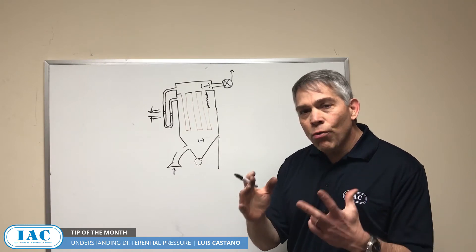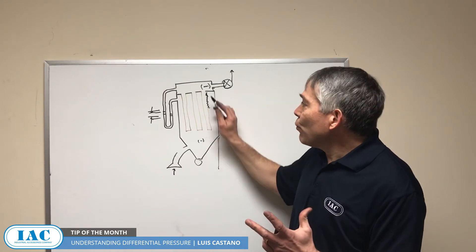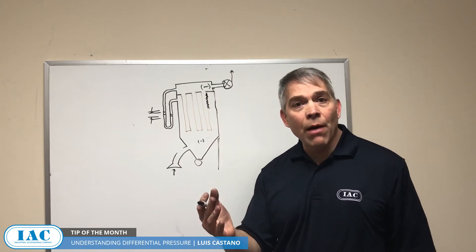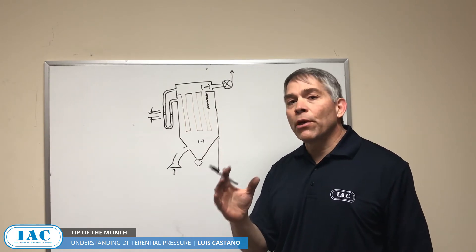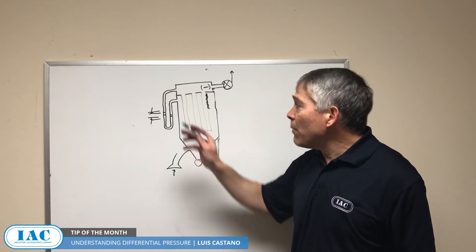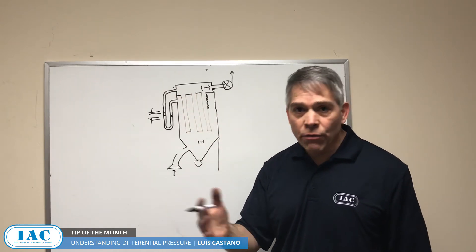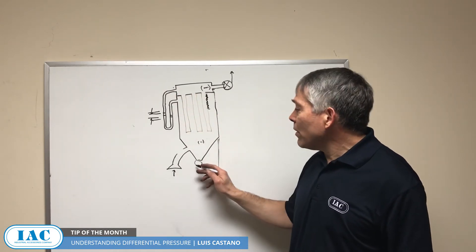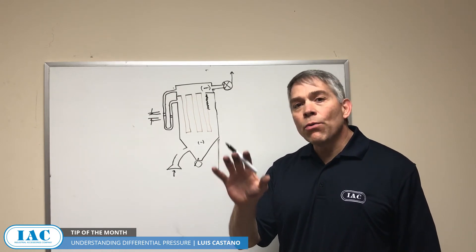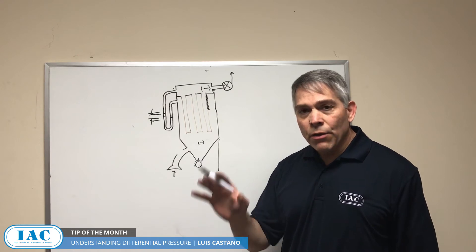The tool that it is for your operation is that if there's too much dust, you have a problem. What is that problem? Differential pressure doesn't tell you, but it warns you that there's a problem. Maybe your cleaning system is off, your compressed air supply is off, maybe you have a leak down here. But at least it's telling you there's a problem and you can go out and troubleshoot it.